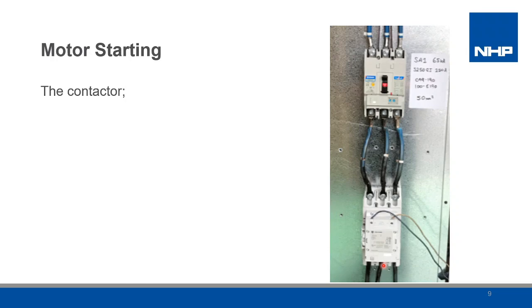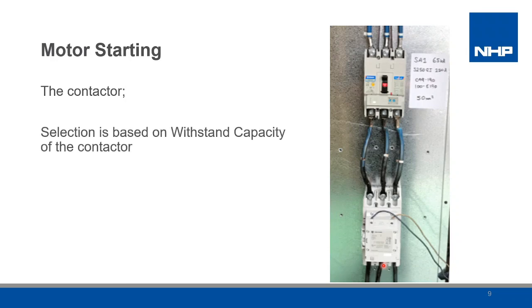The second component is a proposed contactor, which has to be matched to the let-through energy of the short circuit protective device with the fault withstand of the contactor. If the let-through energy of the MCCB is too high, welding or fusing of the contactor contacts will occur as a minimum. Once we have the best estimated selection of a contactor, the combination has to be tested for verification.